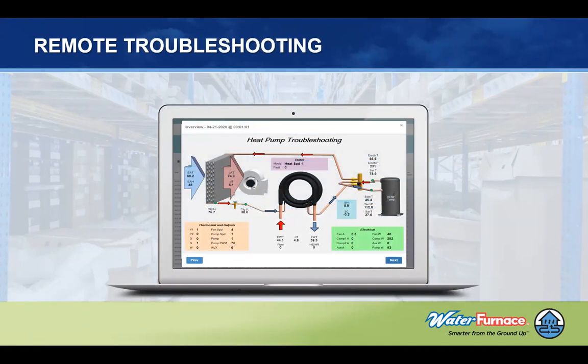And then we can do remote troubleshooting. And this screen provides all of the information that we're looking at on a given piece of equipment. So as we talked about before, the manual method was to get pressures and temperatures and all of that and write them down. From the dashboard on a fully sensored system, we know the discharge pressure, the discharge temperature, and we know the saturation. We know the superheat and the subcooling of the system. We know what the system is drawing from a power standpoint, entering and leaving water temperatures, and then we know what heat of extraction, heat of rejection we're getting. We also know our flow across the air coil and the temperatures.